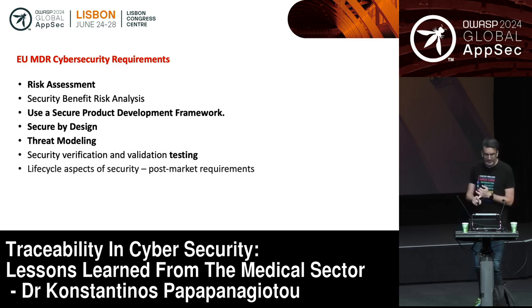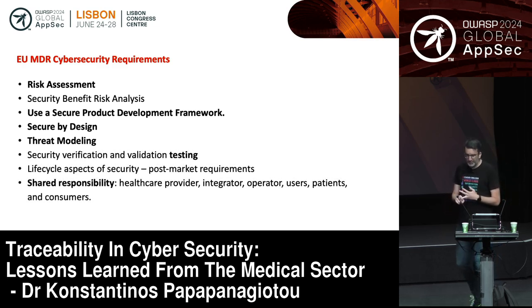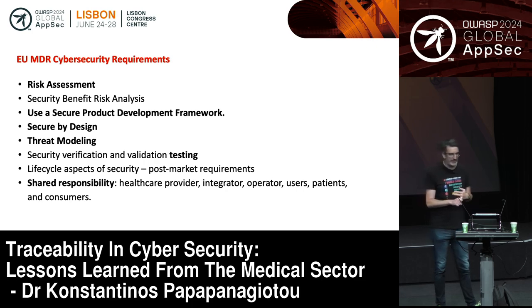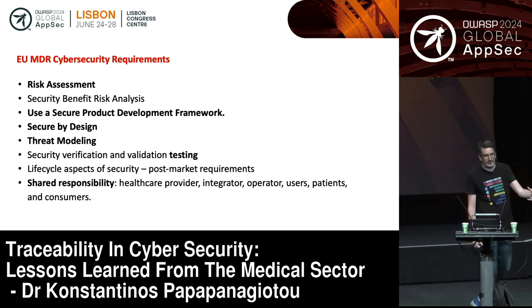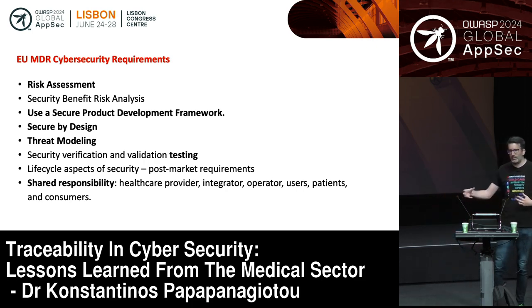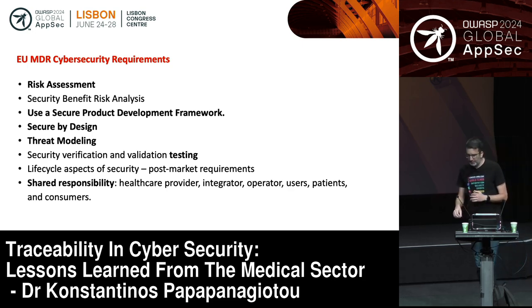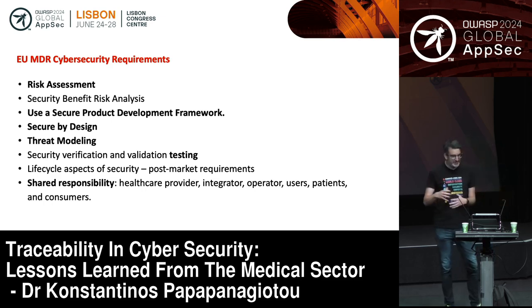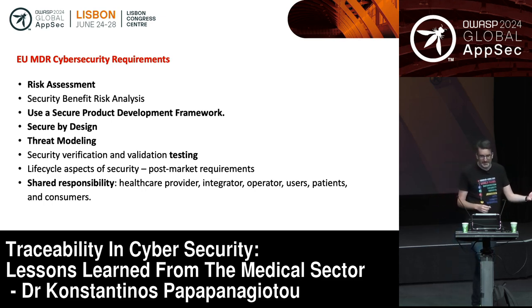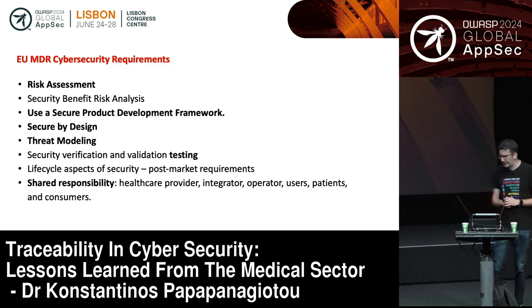So again, you need to do a risk assessment. You also need to do something called security benefit risk analysis. So for every security control that you introduce, you need to justify what the benefit is. You also need to follow a secure product development framework. You need to do secure by design. You need to have a threat model. You need to do testing, of course. You need to take care of the life cycle aspect, the post-market requirements for cybersecurity of the medical device.